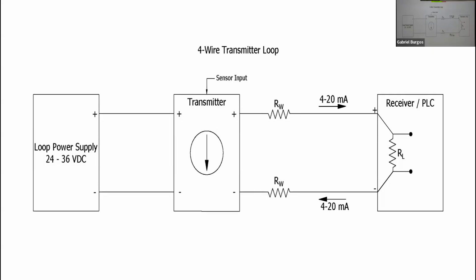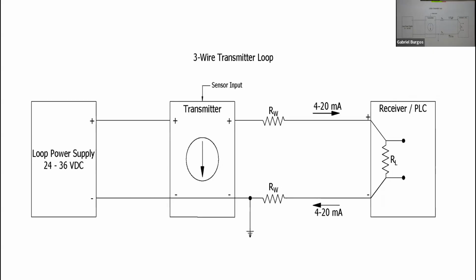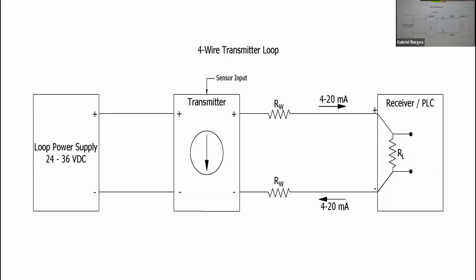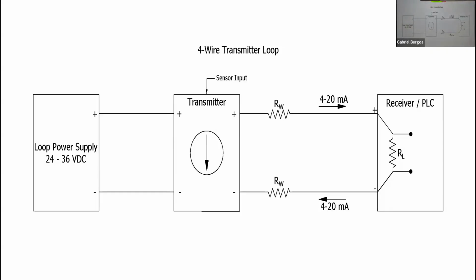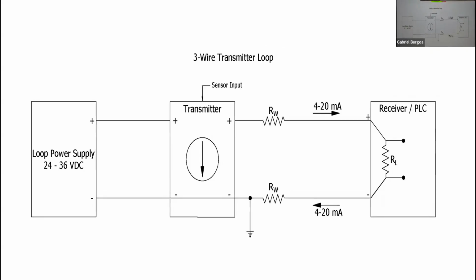Anyway, the one I had before a minute ago. This is a 3-wire transmitter. What happens is you have power coming in, and then you have 2 wires that run out the loop. Okay. All right, here, let's go back. So, notice the 3 wires. You got this wire runs continuously through. We'll call it the ground wire or the return wire. You have 1 wire from the power supply, the loop supply, and you have 1 wire that runs the loop, okay?